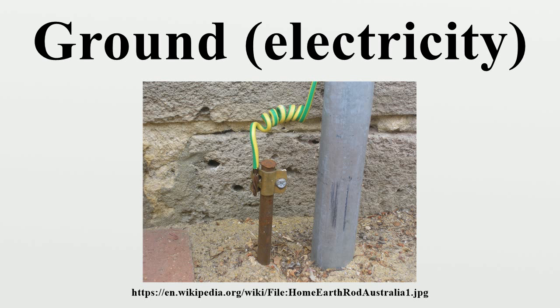Medical systems include monitoring devices to warn of any increase of leakage current. On wet construction sites or in shipyards, isolation transformers may be provided so that a fault in a power tool or its cable does not expose users to shock hazard. Circuits used to feed sensitive audio, video production equipment or measurement instruments may be fed from an isolated ungrounded technical power system to limit the injection of noise from the power system.